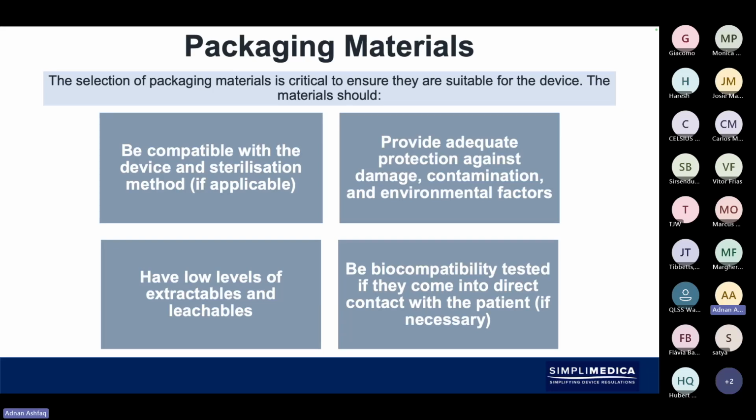Some of the things that you should think about is where the device is to be sold. Now, if the device is to be shipped in a subtropical country or climate, then you should really be thinking about those temperatures and the humidity that's being reached in those areas and regions. And the same thing if it's going into a sub-zero temperature climate, you should also think about the environmental factors that the device will be exposed to under those conditions.